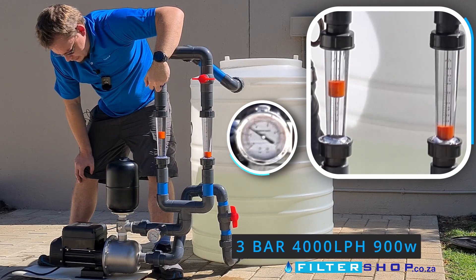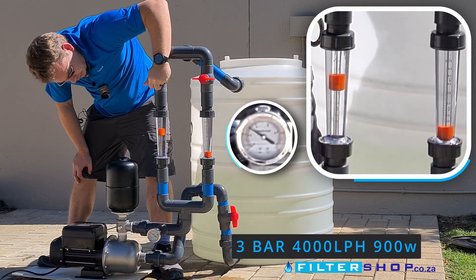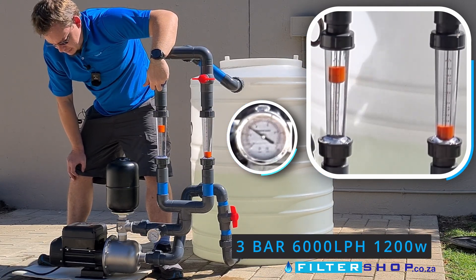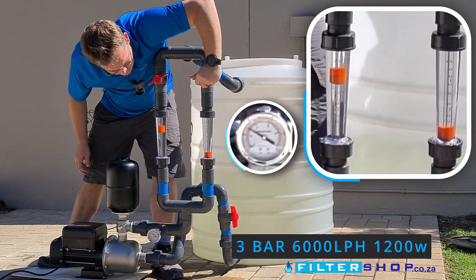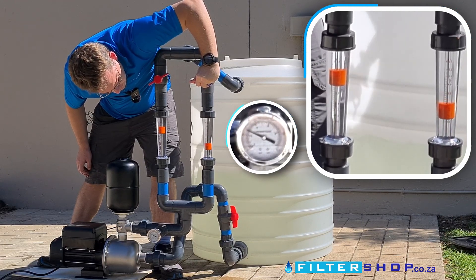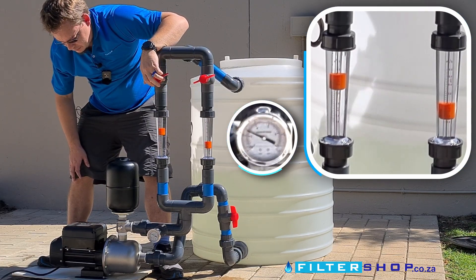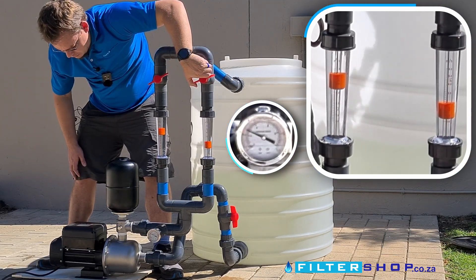At 4,000 liters we're at about 900 watts. At 6,000 liters we're at about 1.2 kilowatts at 3 bar, still maintaining it. We can't do 7,000 liters at 3 bar — the pump maxes out at 1.4 kilowatts and pressure drops down to 2.7 bar.